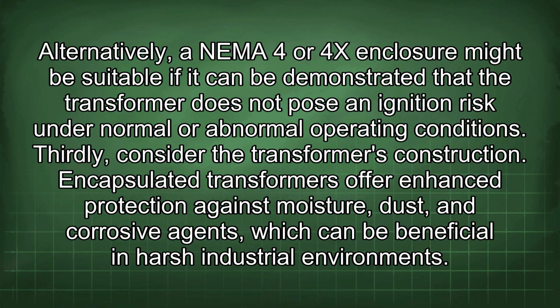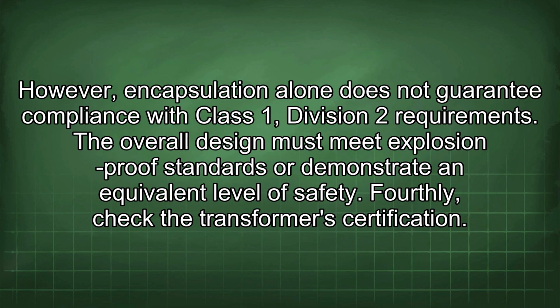Thirdly, consider the transformer's construction. Encapsulated transformers offer enhanced protection against moisture, dust, and corrosive agents, which can be beneficial in harsh industrial environments. However, encapsulation alone does not guarantee compliance with Class 1 Division 2 requirements. The overall design must meet explosion-proof standards or demonstrate an equivalent level of safety.